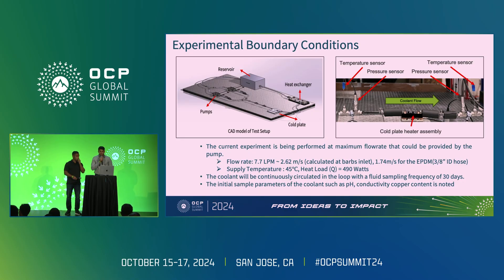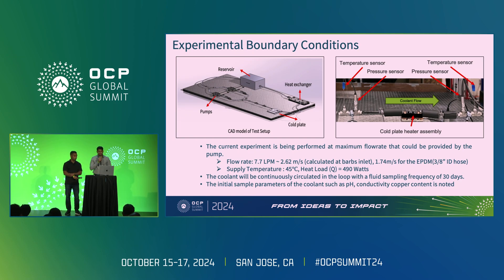We installed a few pressure sensors and temperature sensors before and after the cold plate, which will help us determine the thermal performance and hydraulic performance of the cold plate throughout the testing period. There is also a thermocouple present on the heater base, which gives us case temperatures to help us with thermal resistance. Initially, at day zero, we collect a sample from the reservoir, which gives us the baseline parameters of the coolant, such as pH, conductivity, turbidity, and the copper content present in them.